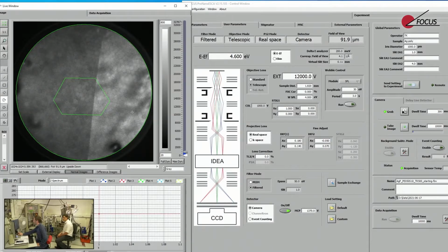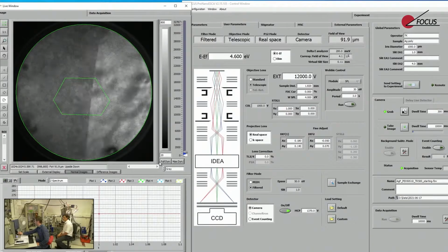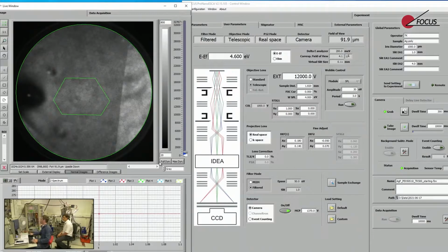I will move a little bit to the right, and you see the next grains I plan to investigate are a little bit wider than this size, so that's actually the reason. It's about 30 microns in diameter, this iris aperture, and the highest performance in k-space you will get actually already with 30 micrometers. If you go lower, you can improve a little bit, let's say 5%, but between 30 and down to 10, it's the best performance. You could go even lower to a few micrometers. We will come to this later.